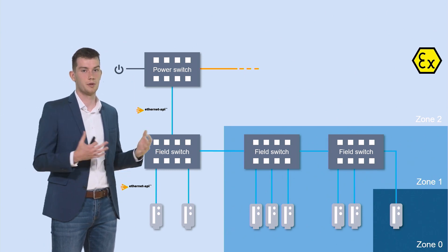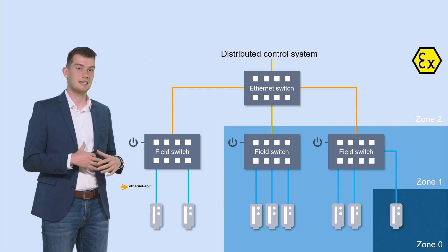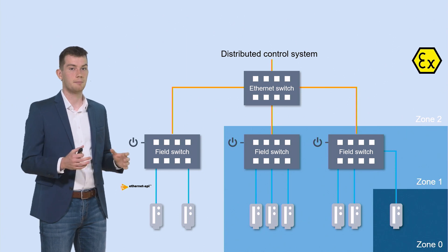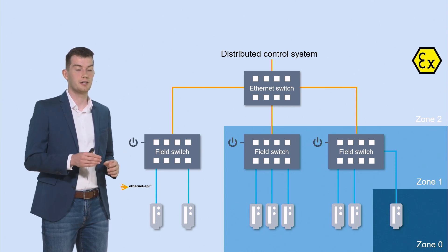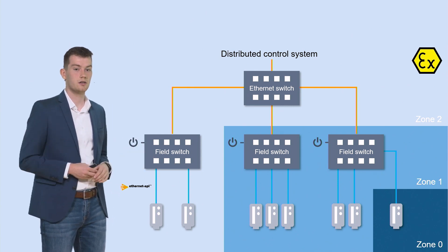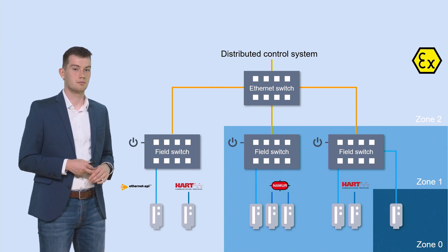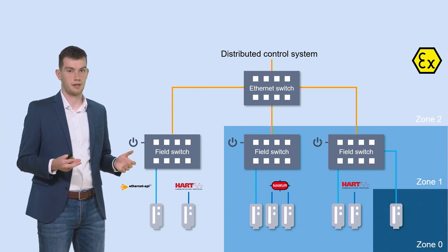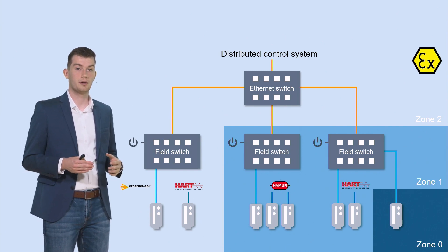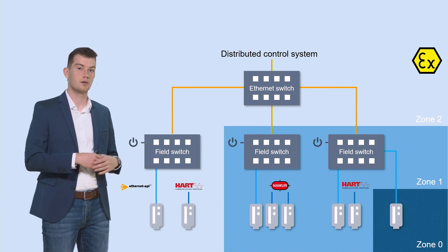But all of that is just a vision right now. The current status looks different — we have a standard Ethernet backbone with no power switch included. We just use the field switches, connect them directly into the Ethernet backbone, and feed them externally. As a requirement for this architecture, all the field devices need to be APL capable. But this is not the case right now. We do not have enough APL-capable field devices on the market to deploy APL across current or new plants.